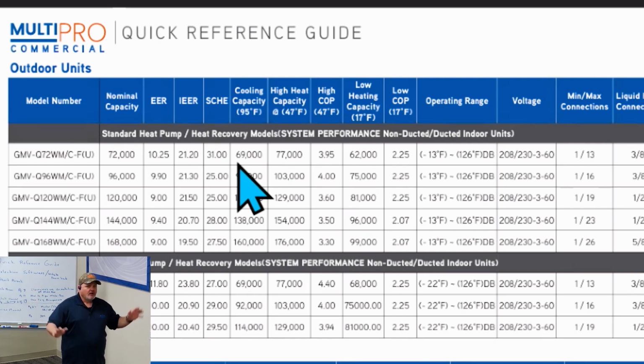Right, and then there's a lot of redundancy too - like if you have a server room application, a lot of times they'll have a system that's the primary cooling system for that server room, but they also have a backup, because they can't afford the machines to go down. So you can still use 2 machines there - one machine absorbing heat out of it and providing heat to the other part of the building, and the other one's redundant, doing the same thing.